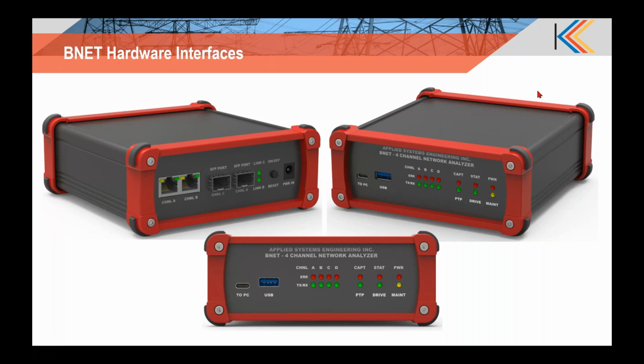I have one question that has come up. Can you simulate typical faults other than over and undercurrent and voltage? For example, simulate the SV streams needed to trigger a distance protection fault or differential protection fault, under or over frequency. Right now we don't simulate the frequency, but that is one feature we could add. Definitely, that was a request we had from some other customers as well. We can add it into the roadmap, but right now we don't simulate complex protections.